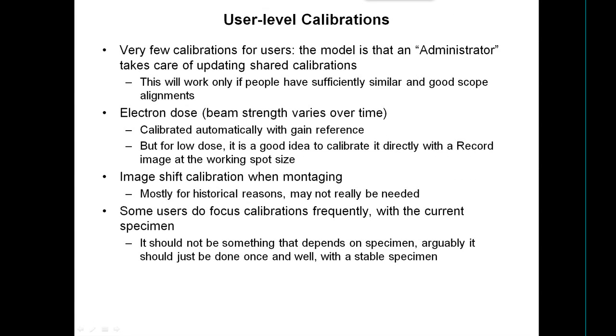Very few calibrations are ones that users themselves need to worry about doing, because the model is that you have one administrator who maintains the shared calibrations. This only works if you have sufficiently similar and good scope alignments. On the FEI approach in our lab, we periodically have service save an alignment, or someone touches it up and saves it, and we tell everyone: load this alignment. Then they do their daily tuning, and we're all in a very similar state — and things work very well.